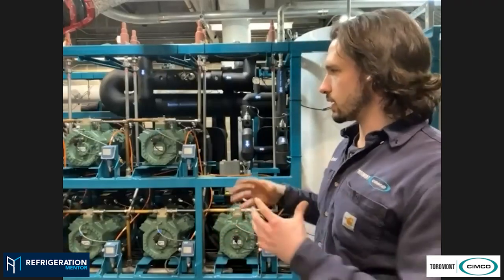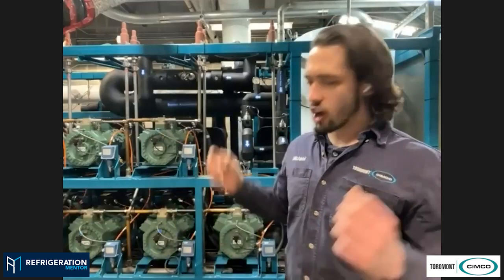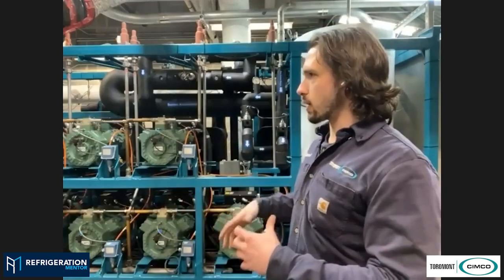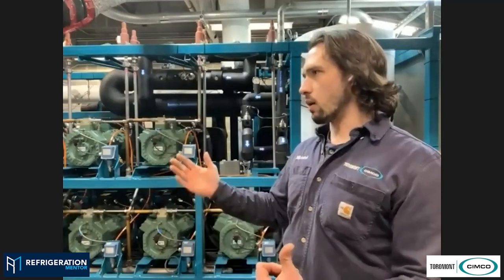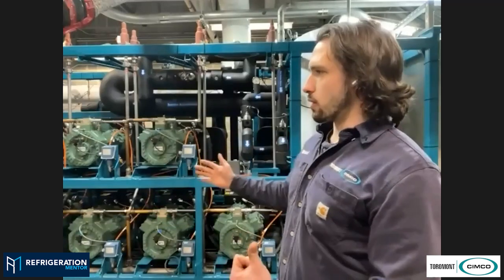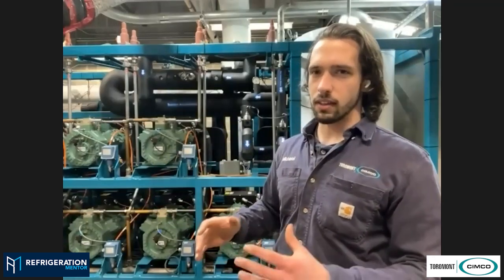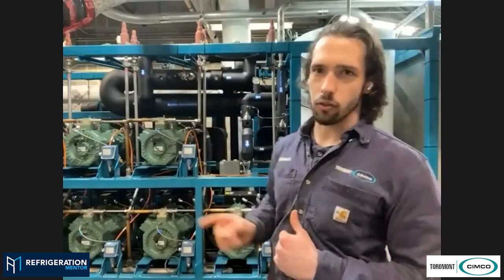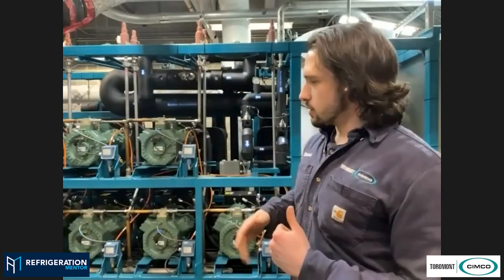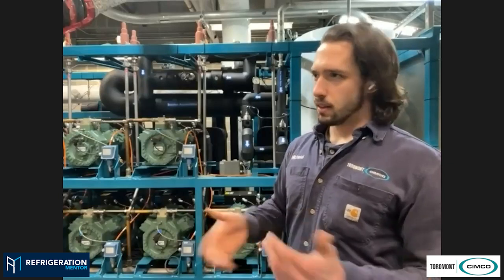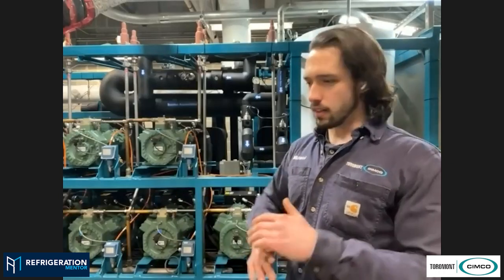Because in my opinion, the conditions are so stable on an ice rink, you have a giant slab of ice out there, a giant thermal mass. For the most part, the ambient conditions outside aren't swinging up and down like crazy, they go up and down with the day. The system runs very, very smooth. Honestly, the biggest fluctuation is when those valves open up to recycle gas, you get a minor change in superheat, the valve drivers respond, and then things even back out again. Other than that, this is an ideal scenario for a CO2 chiller, in my opinion - an ice rink.